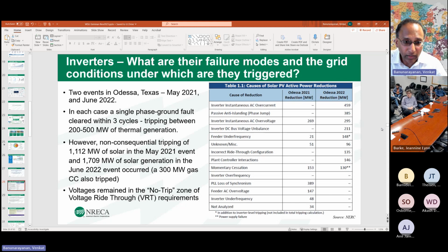So ERCOT tried to do so. What ERCOT did was, after the first disturbance in 2021, they did those simulations, and they were able to avoid some of the reasons for tripping during the second time. But then they found a bunch of new reasons for which the inverters tripped the second time.